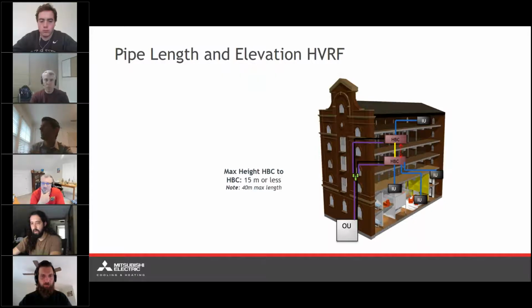Again, all this is just numbers at this point, but this is where I want to really drive it. The max height between these HBC controllers. So we can have up to about 45, 50 feet between these HBC controllers. So if you're running into a circumstance where the vertical separation of your fan coils on a heat recovery system gets too great and you're exceeding the limits, well, that pretty much means we can only have a maximum of 4, 5, 6, however many floors on that particular system, whatever the line lengths you're going to be encountering.